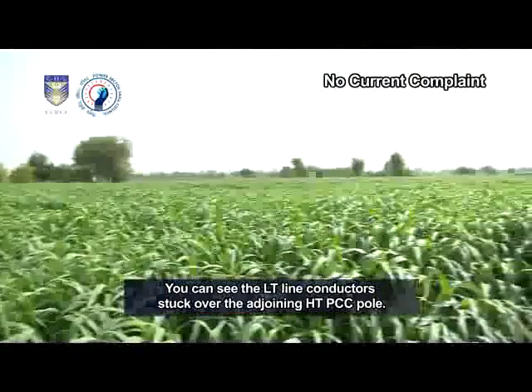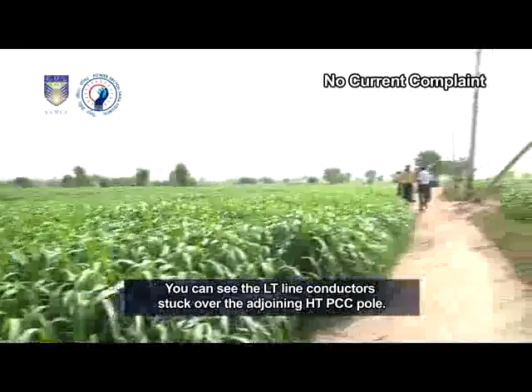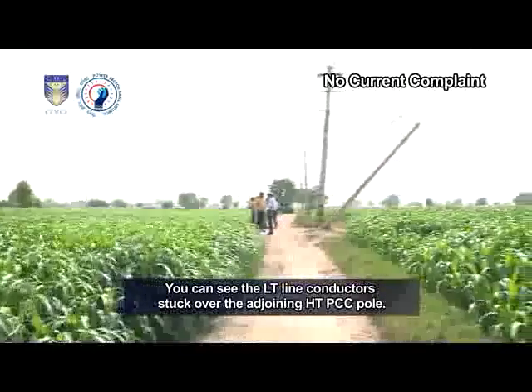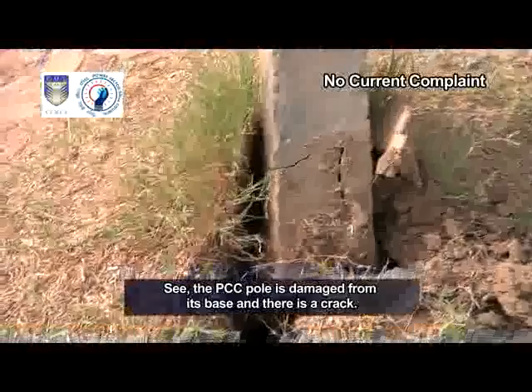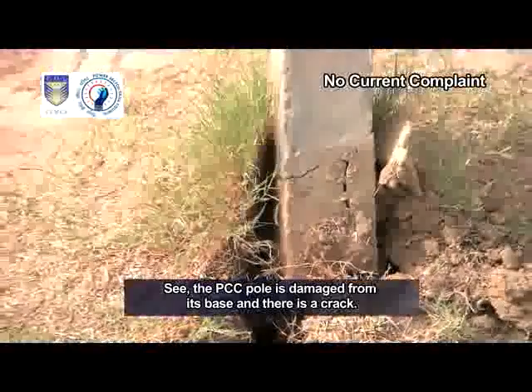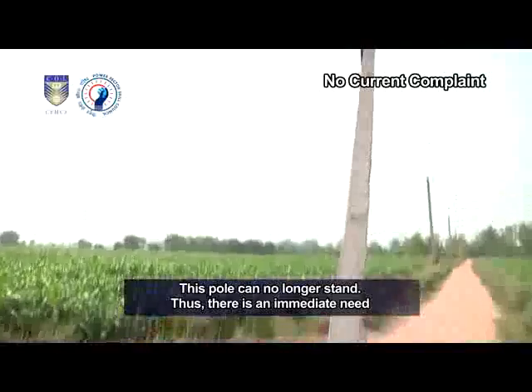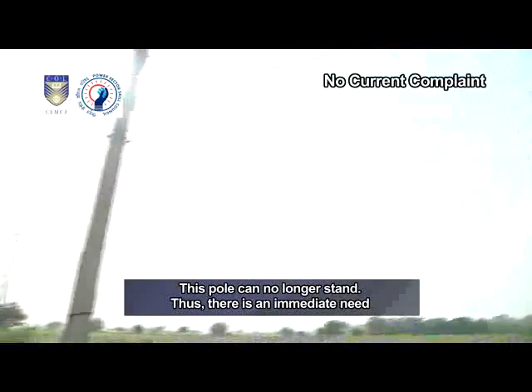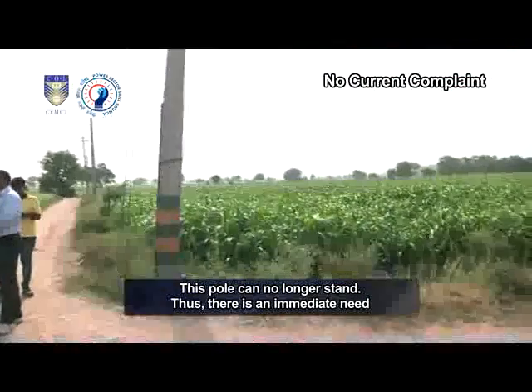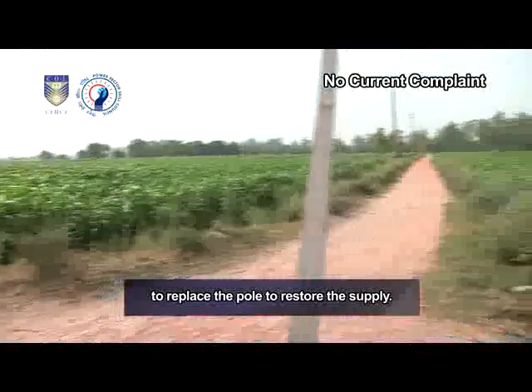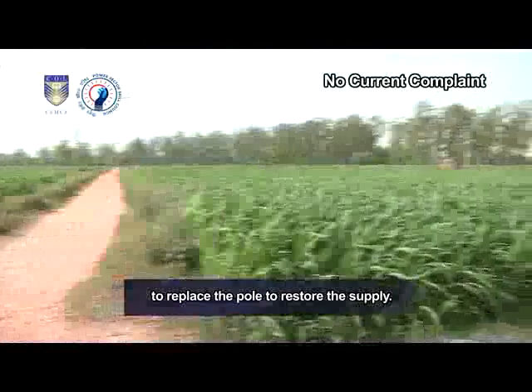You can see the LT line conductors stuck over the adjoining HT PCC pole. See, the PCC pole is damaged from its base and there is a crack. This pole can no longer stand. Thus, there is an immediate need to replace the pole to restore the supply.